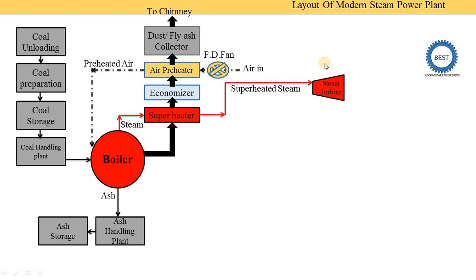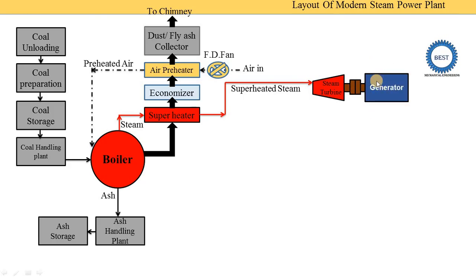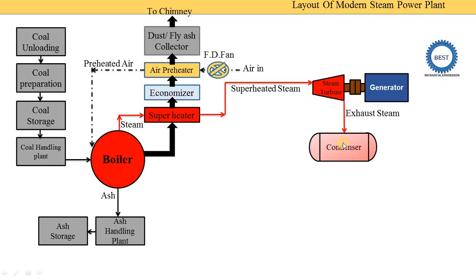In the turbine, the energy of the steam is converted into mechanical energy. The turbine has three stages: high pressure, intermediate pressure, and low pressure. The mechanical energy produced by the turbine is supplied to the generator, which produces electricity. So the chemical energy of coal is ultimately converted into electricity. The exhaust steam from the turbine is supplied to the condenser. The condenser is a type of heat exchanger where condensation occurs — steam is converted into liquid, called condensate.